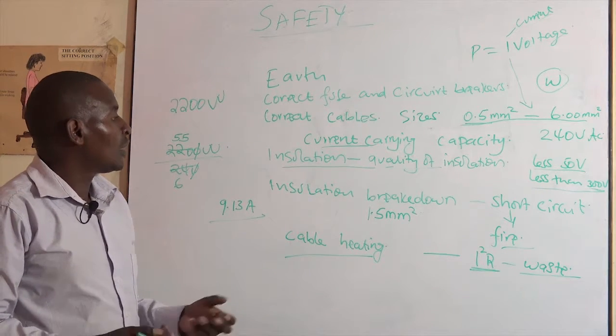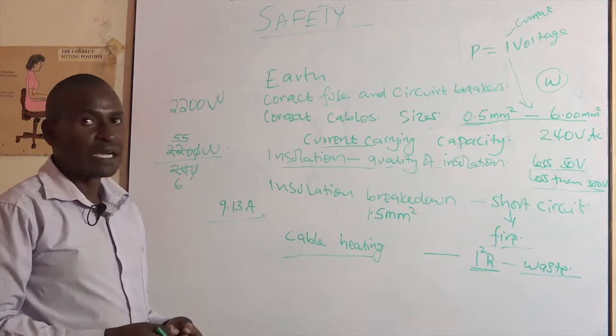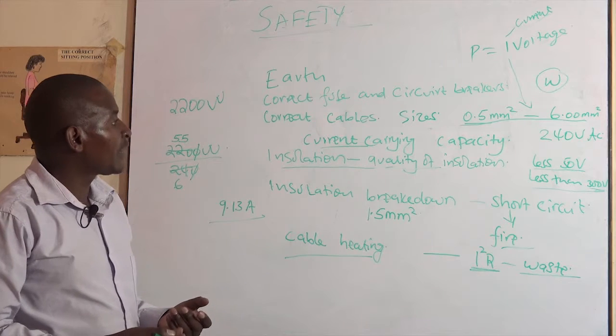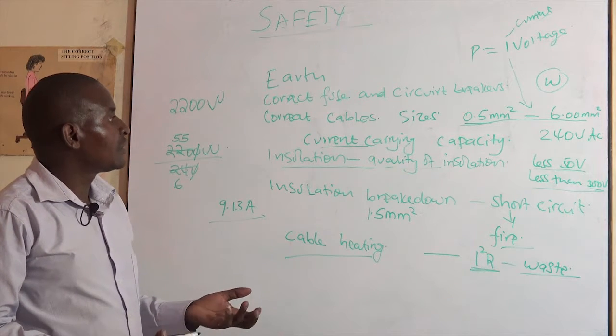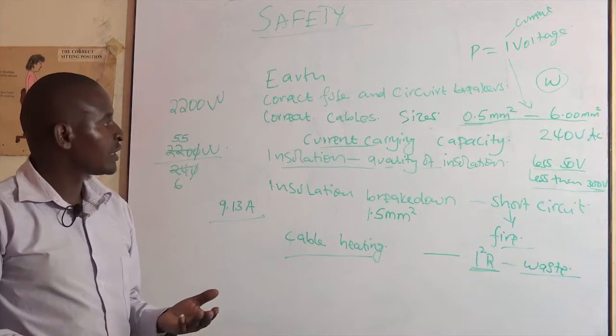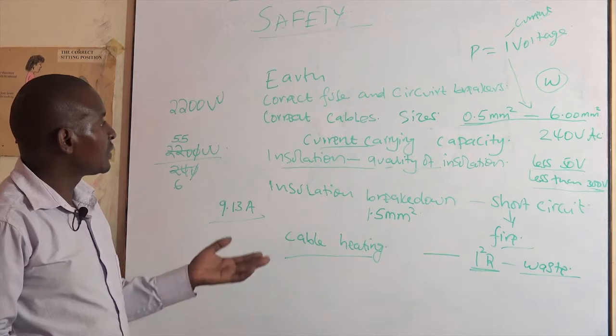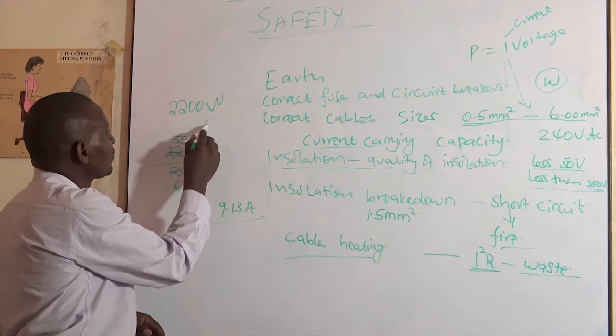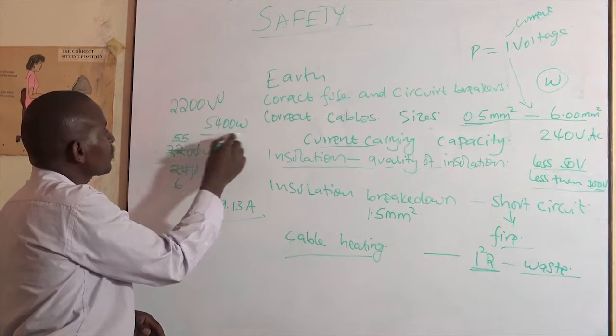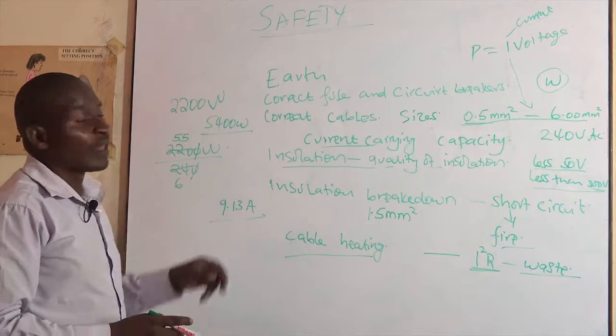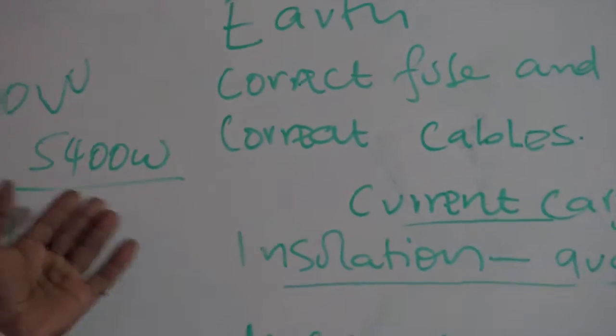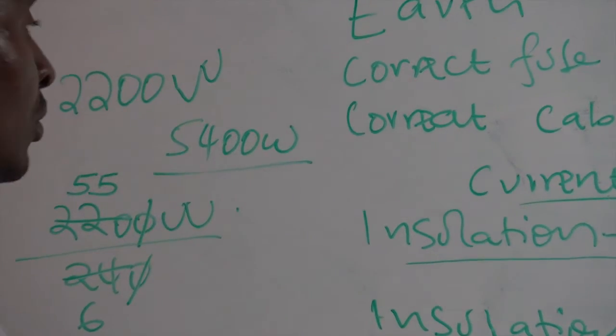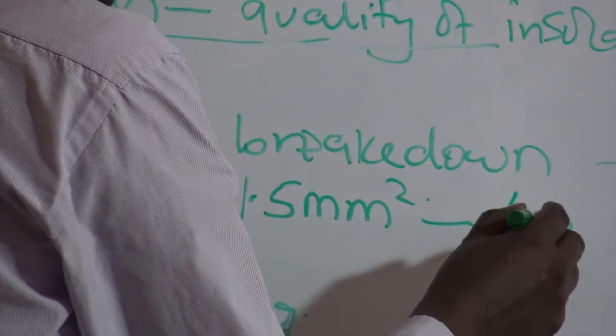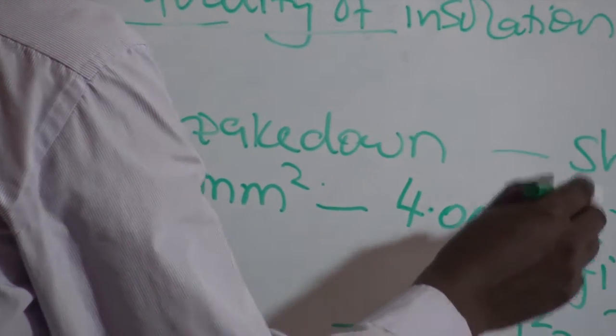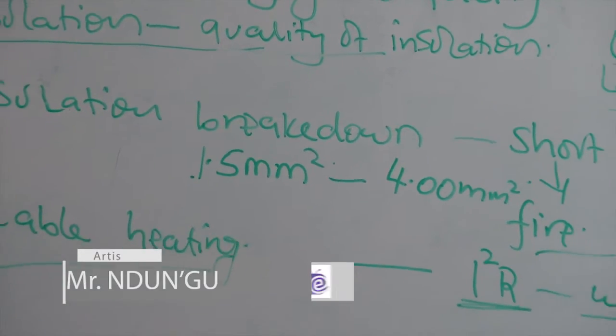Like now, if you want to supply maybe a shower unit that you don't know the rating of, then the best thing you can do is get someone who is able to do that. Some of the shower units are rated quite high, which means that if you divide the rating by 240, you get that the cable required might go to 4.0 millimeter squared. So that's what should be understood.